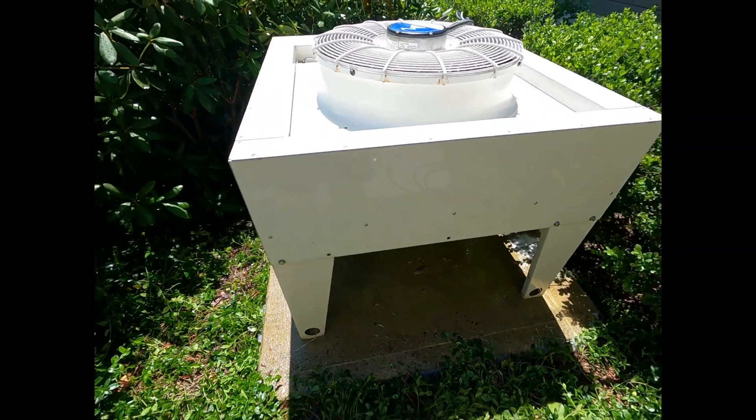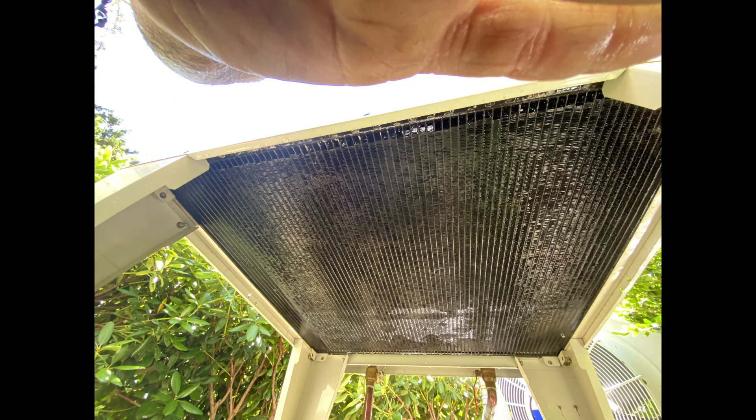The coil is nice and clean — a little wet but clean, will dry fast. It's only hot water going through, not refrigerant. System is all cleaned up, coil can breathe again. System is operating perfectly again. Until next time.